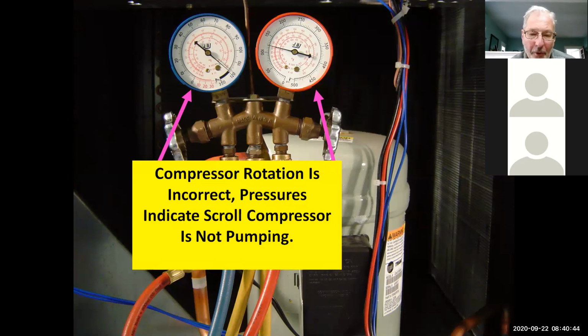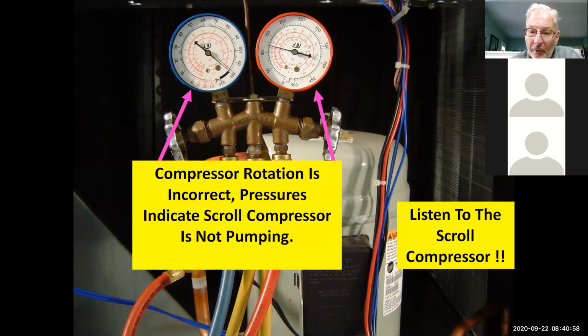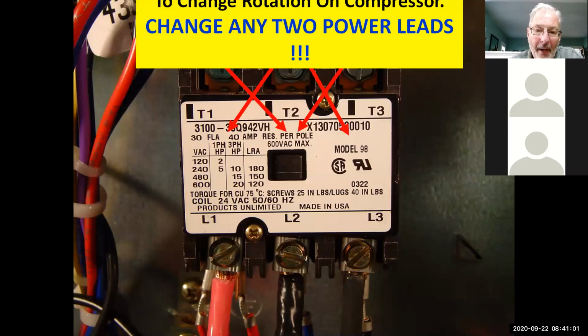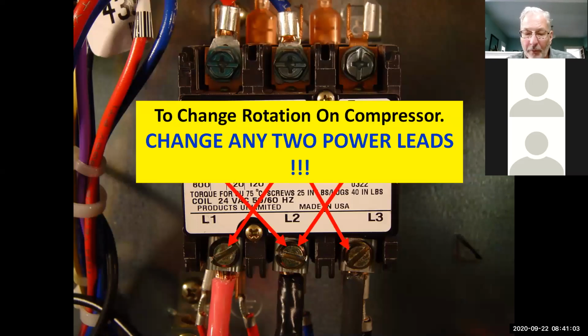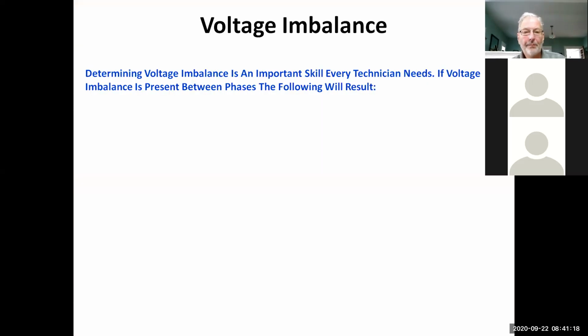When you fire these up, throw your gauges on there. If they're noisy and they're not pumping, they're running backwards, and they won't run long like that. But the best way to check them is to just put your gauges on there, make sure we're pumping, make sure they sound like they're working properly. Listen to the scroll. On a three-phase system, reverse any 2 wires, and you've reversed the rotation of the compressor or the system in general. So make sure that if you're going to change rotation, you switch any 2 of the wires.